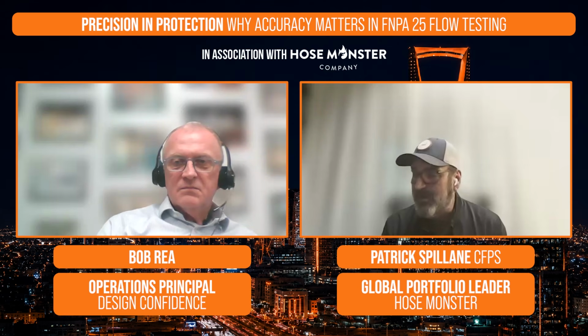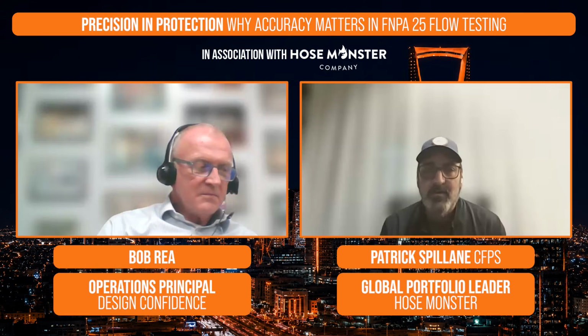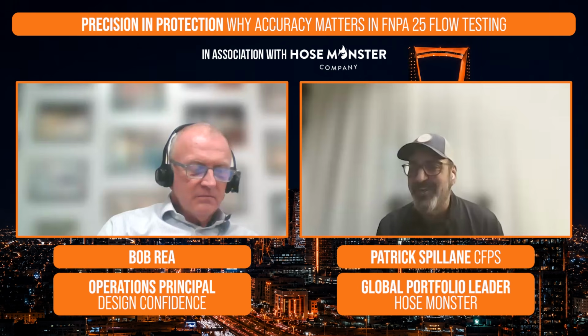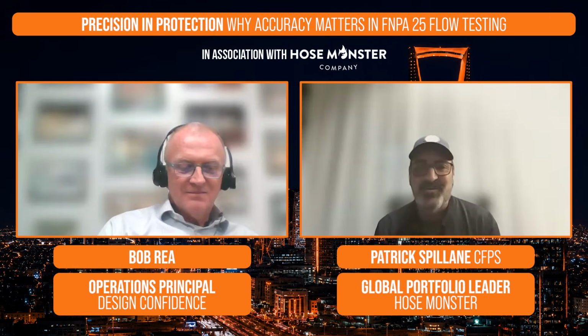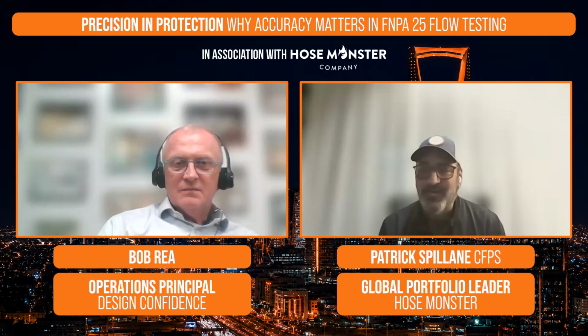However, if you suspect anything is wrong with that fire pump, go ahead and make sure you speak with your customer. Doing a full flow test at any time if you have any concerns about that fire pump, you don't have to wait a year to do it. Even if we just did an annual flow test last month, if you're seeing something with that fire pump that leaves you any concern at all, please take the next step in making sure that customer is being led down the correct path for maintenance. And yes, you do another flow test as soon as possible.